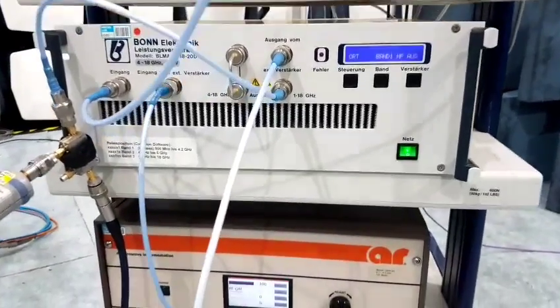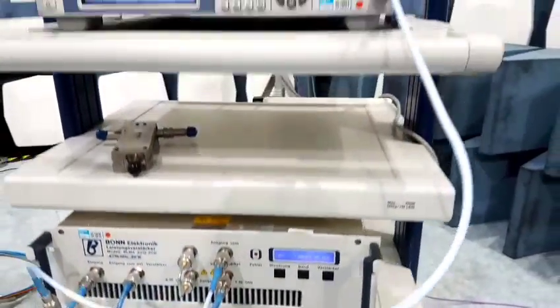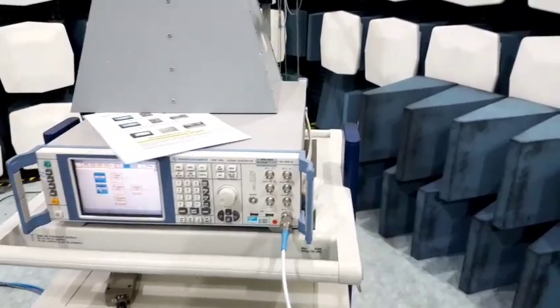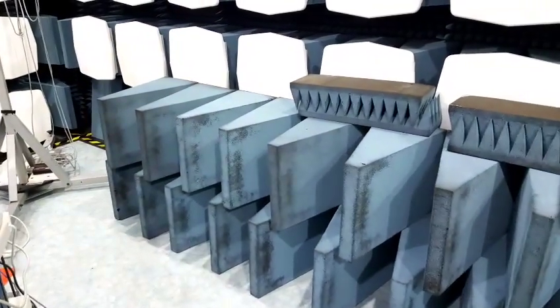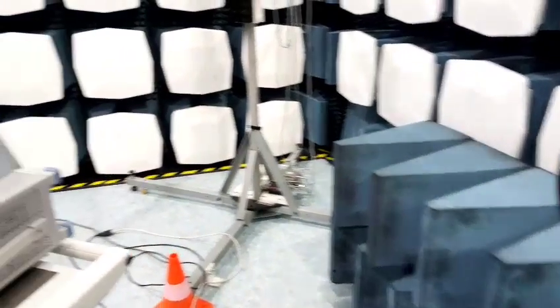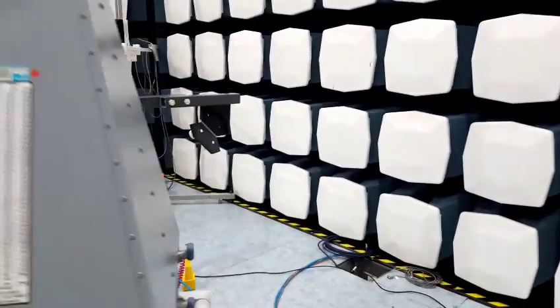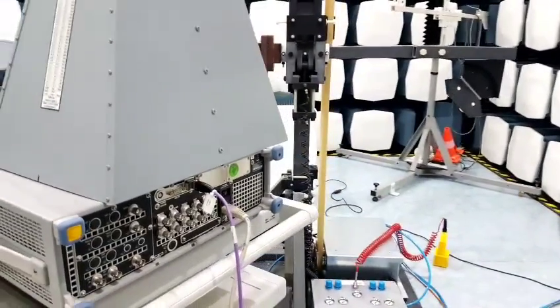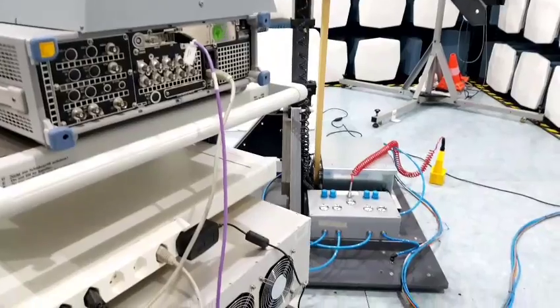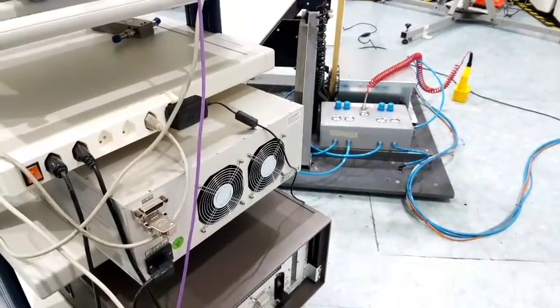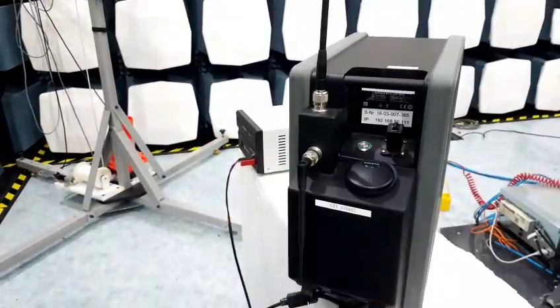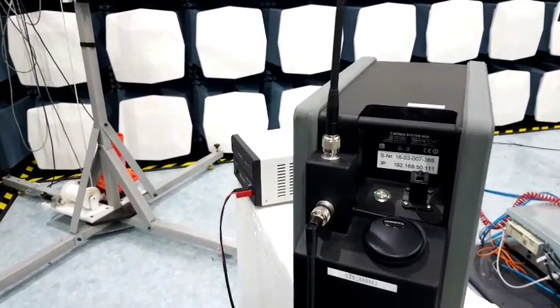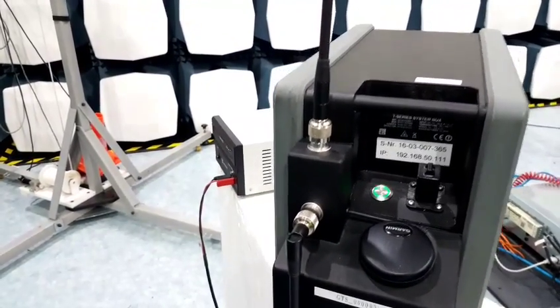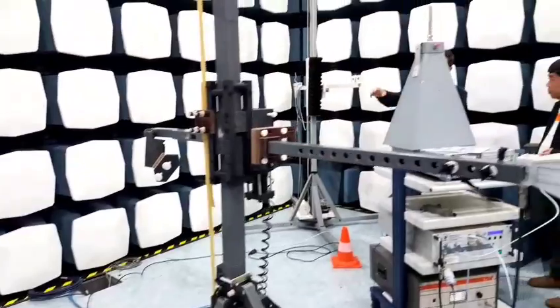We also have the Helmholtz coil here, and we calibrate in special ranges, for example 10 kilohertz to 400 kilohertz. This special mast here is used for antenna calibration — we place it in the chamber, on the side.